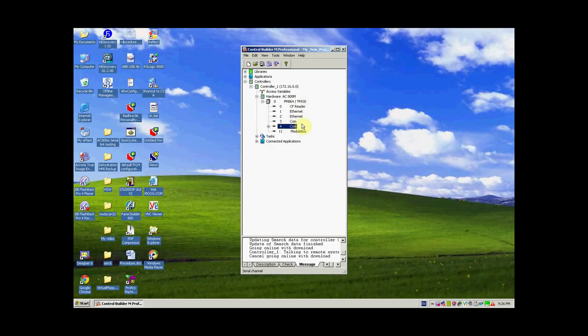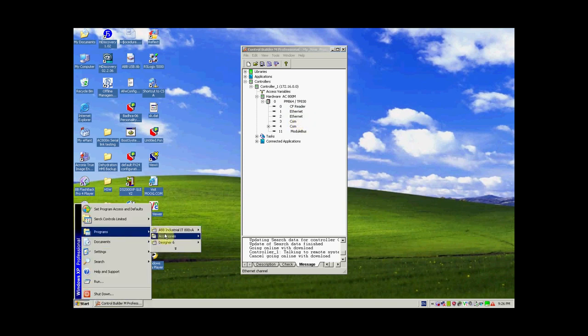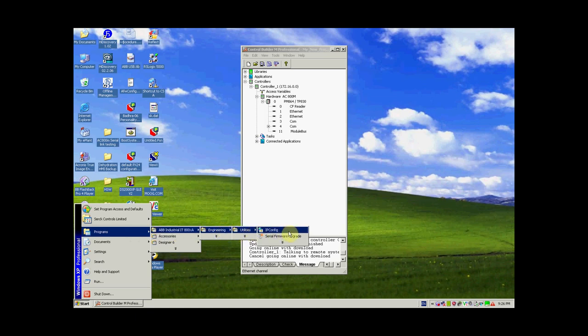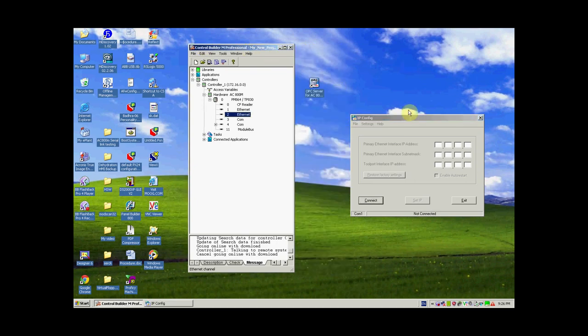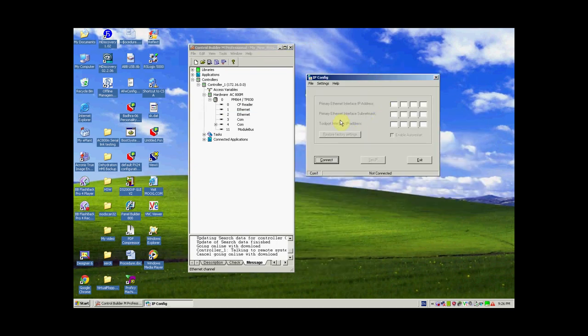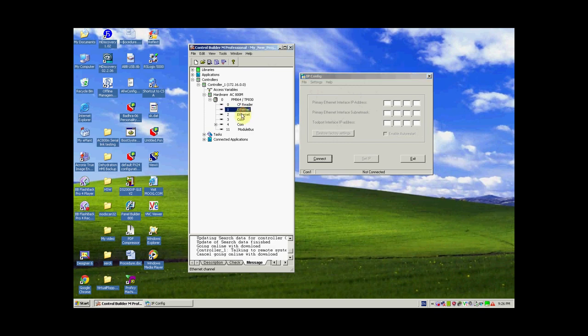To assign an IP address on CN1 and CN2, go to Start, Programs, ABB Industrial IT, Engineering, Utilities, and open the IP Config program or utility. This is the IP Config interface where we are going to introduce an IP address to the AC800M controller on CN1 and CN2.